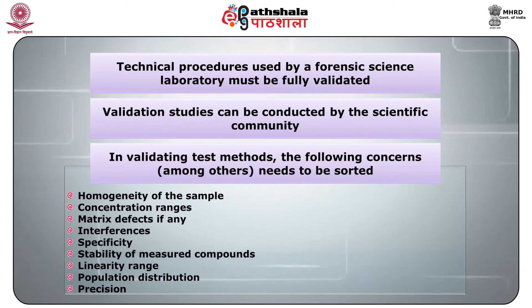In validating test methods, the following concerns, among others, need to be sorted out as appropriate: homogeneity of the sample, concentration ranges, matrix effects if any, interferences, specificity, stability of measured compounds, linearity range, population distribution, precision. Methods developed in-house for both qualitative and quantitative work must be validated by the laboratory before use.